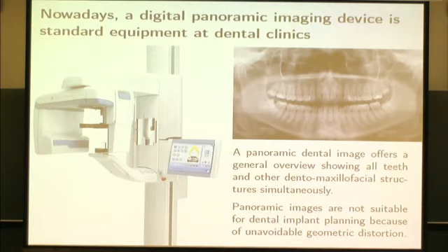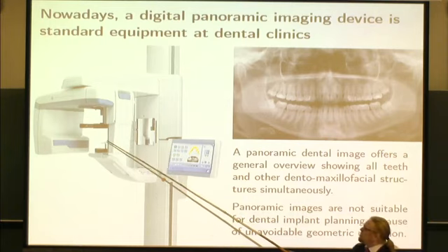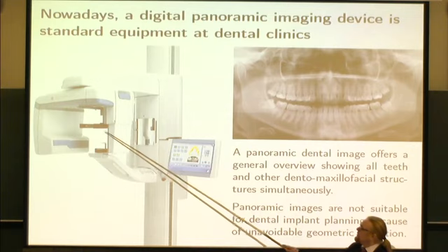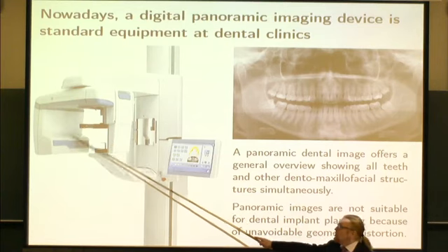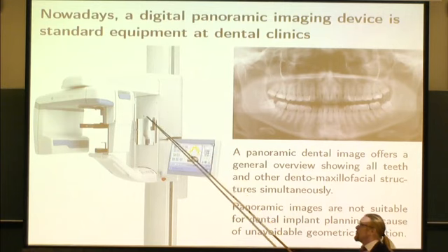One option could be to use, for example, a panoramic imaging device, actually invented by a Finnish professor, Yrjö Paatero, in the 50s. He founded a company called Palomex, which later became Instrumentarium, bought by Instrumentarium and so on. This was the main product of his. The idea here is that the head is here, you bite this thing here, these come to the temples, the X-ray source is here, the whole device rotates around the head.